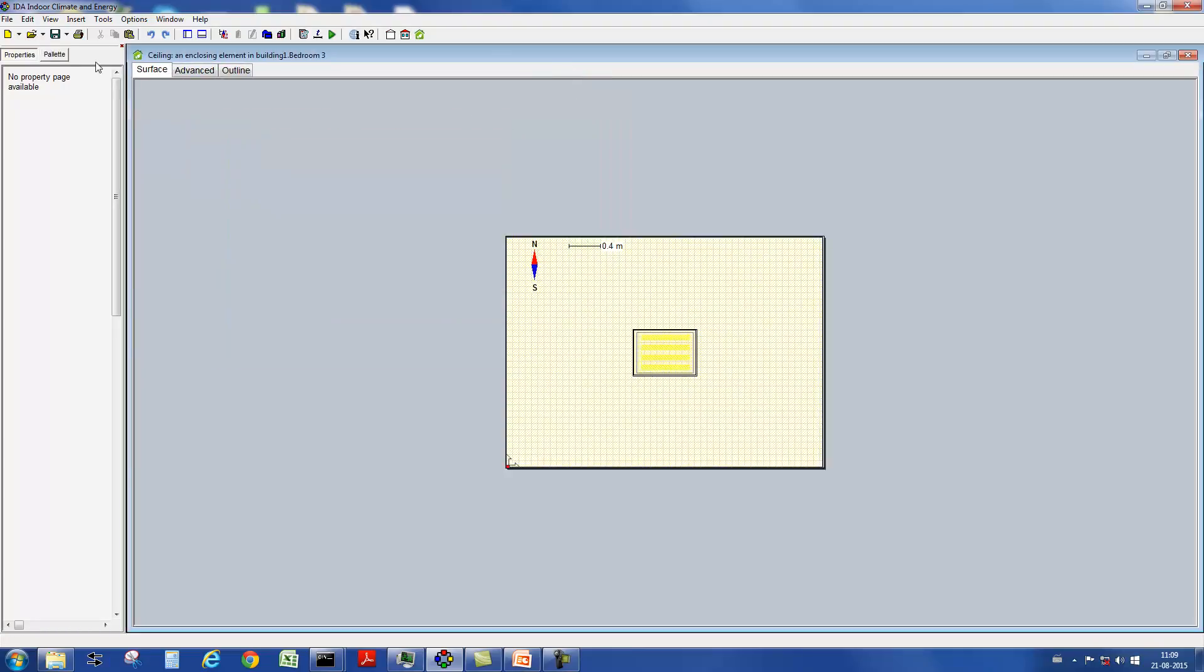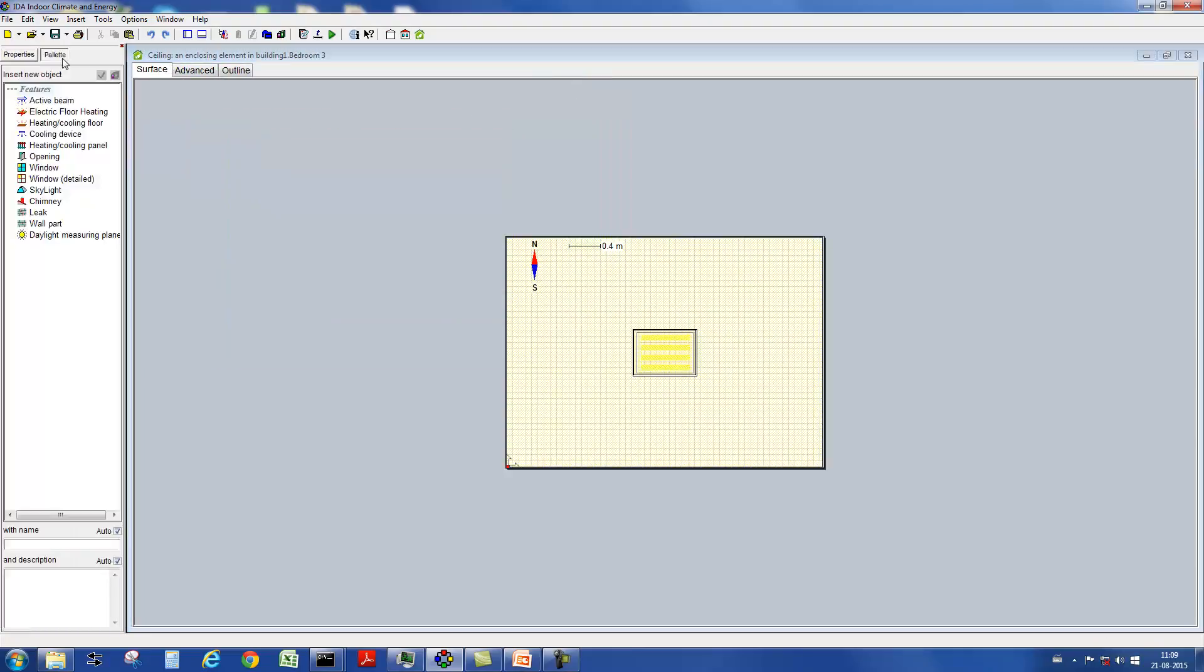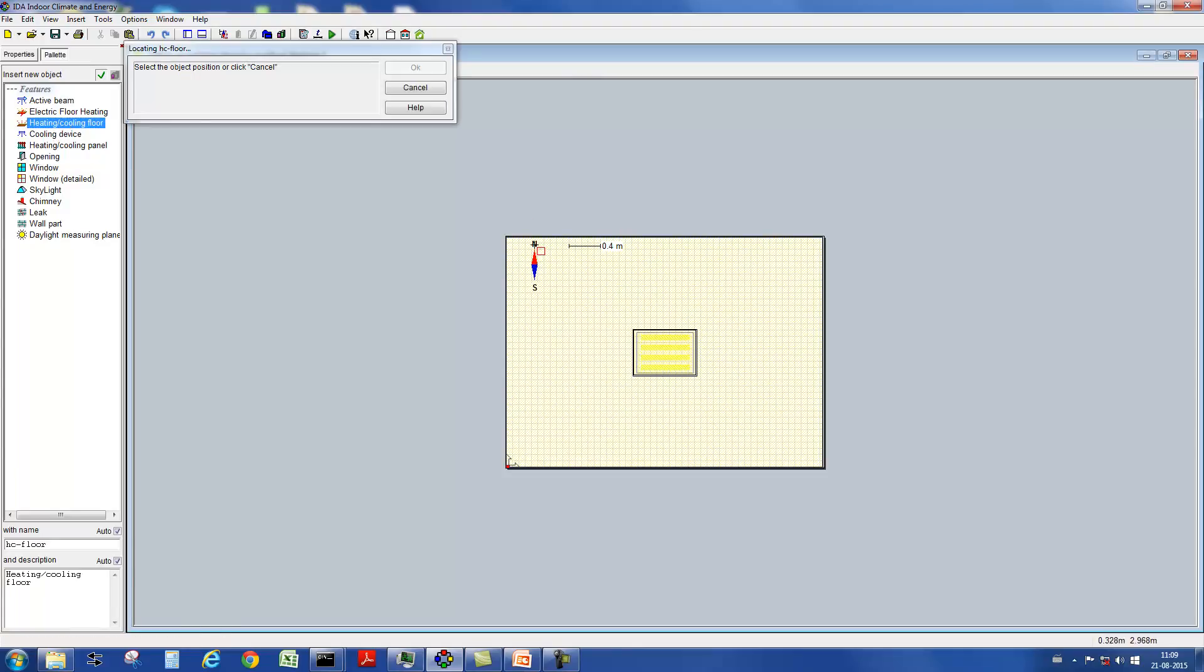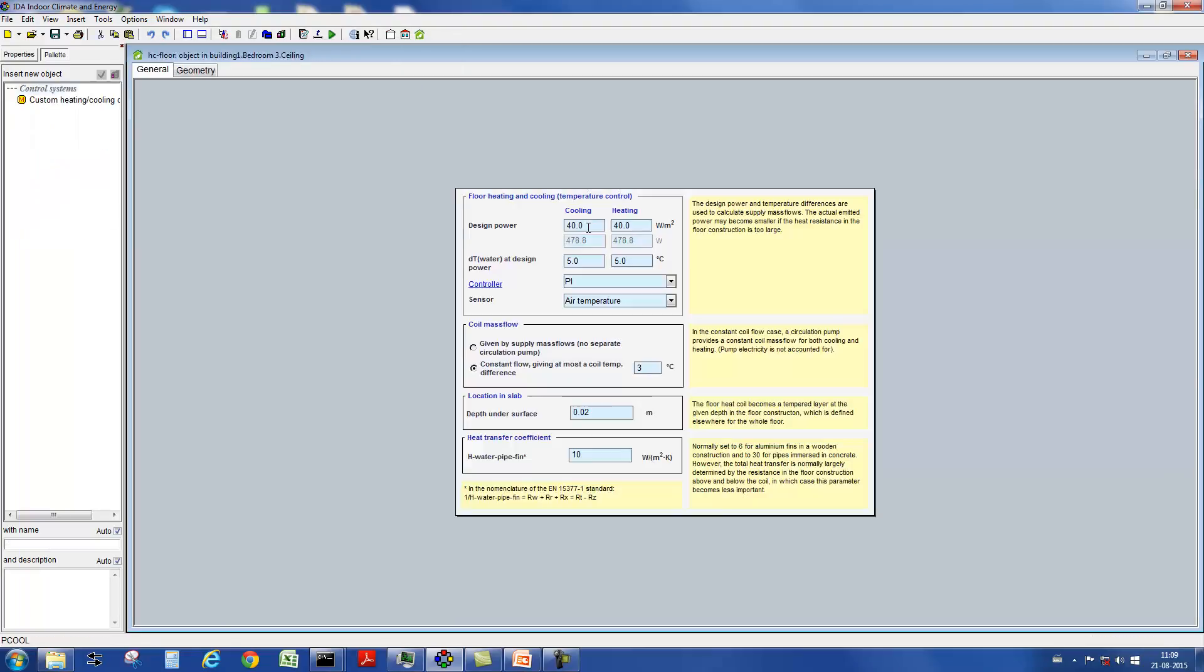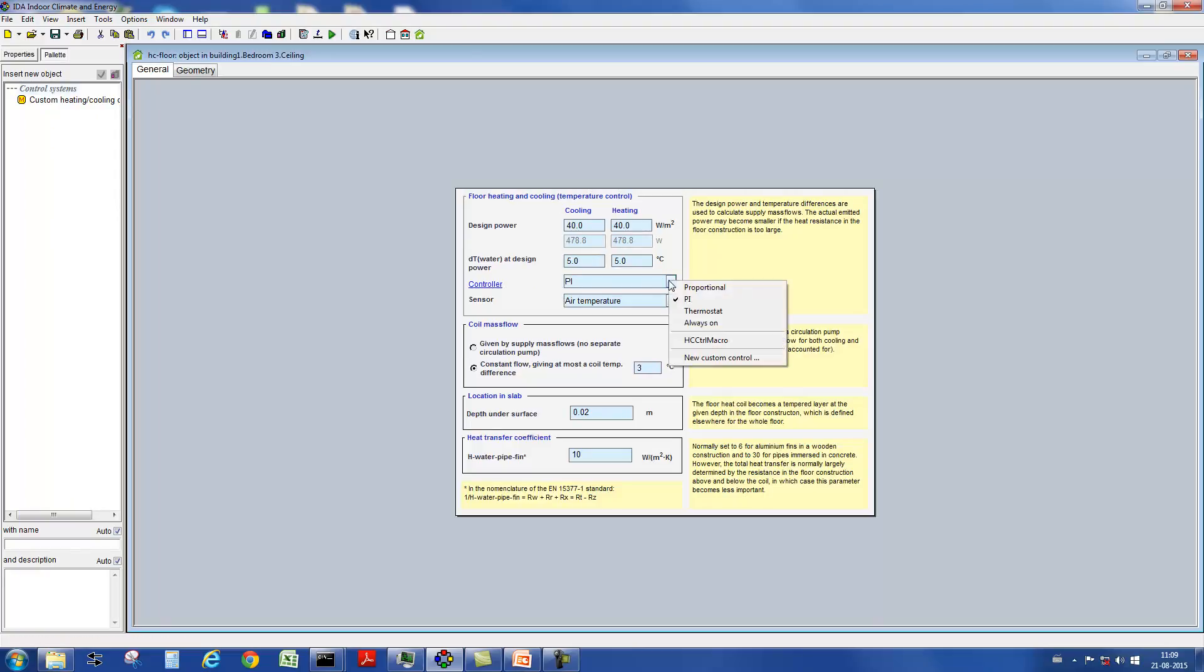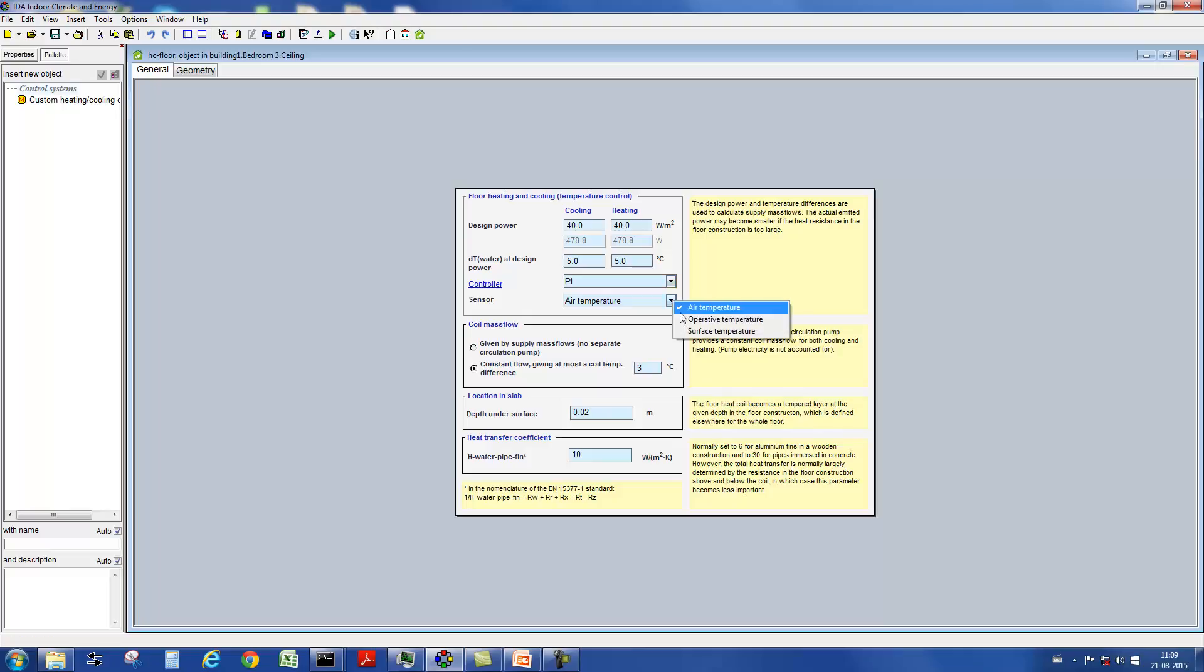Let's take for example thermal active building systems. These are included by the user directly in the slab. Different parameter settings are possible: the power under design conditions as well as the delta T of the water under design conditions. In addition, the type of control and the sensor type. The depth under the surface is also specified.